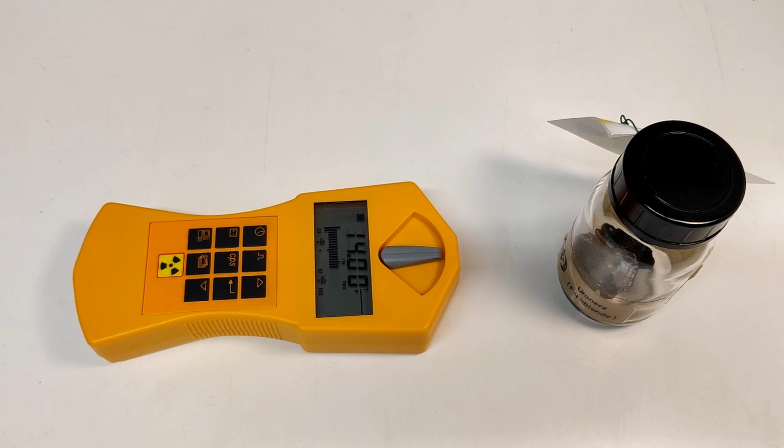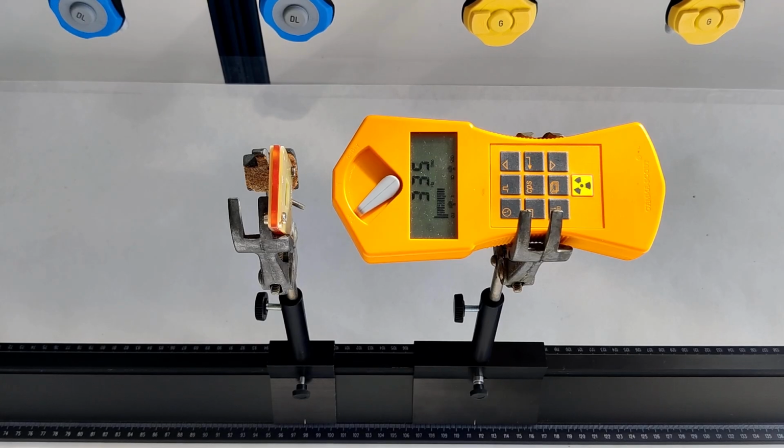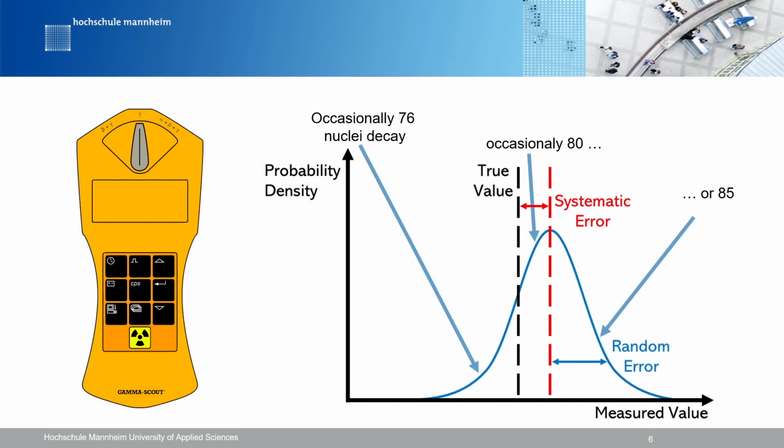This is one of the reasons why we observe fluctuating count rates during our example measurements. Such discrepancies are particularly pronounced, especially during brief measurement periods, with a limited number of detected pulses, as evident in measurements of ambient radiation, for instance. The lower the observed number of counts, the larger are the deviations. The fewer measurements taken, the more pronounced any change in the measured value seems. In such cases, optimizing measurements to count more pulses helps creating a more accurate approximation to the true value. When we compare the measurement of ionizing radiation to our example with the scale, we can draw several parallels, shedding light on the similarities between two measurement processes.